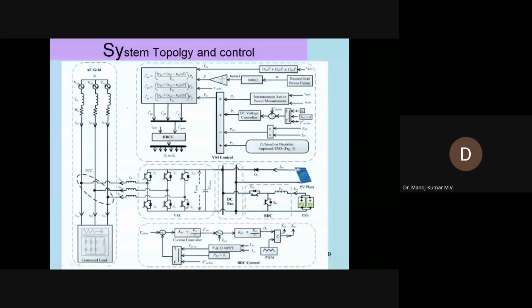Moving forward, I said the instantaneous load power is supplied, but if you look at the position of the inverter connected here, in addition to the load power, the inverter has to do some more functions. It has to inject the power from the PV, and it has to control the charging as well as discharging power of the battery. So this also has to be added in the power component in the controller. In addition to the load power, the PV power and also the power from the battery are added or subtracted based on the charging or discharging nature of the battery.